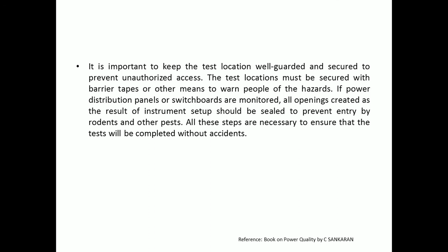It is important to keep test locations well guarded and secured to prevent unauthorized access. The test locations must be secured with barrier tapes or other means to warn people of hazards. If power distribution panels or switchboards are monitored, all openings created as a result of instrument setup should be sealed to prevent entry of rodents or other pests. All these steps are necessary to ensure that the test is completed without accident.